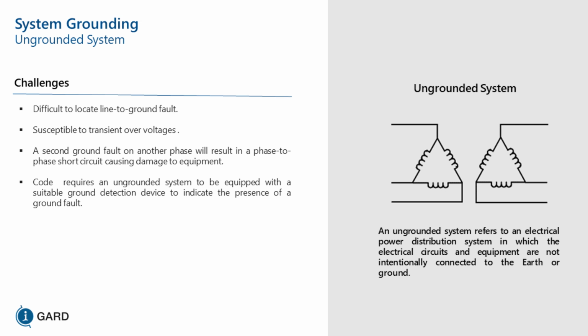So we're susceptible to transient overvoltages in an ungrounded system because, think of it as charging the capacitors of your system. You have an arcing fault, you're constantly charging and discharging the capacitors, and depending on the time of that fault, you could be arcing at the positive cycle of the AC wave or the negative cycle of the AC wave. So you're constantly changing the voltage on those capacitors, and you can have 6 to 8 times normal system voltage with respect to ground. If a second fault occurs, then you have a phase to ground to phase fault, and something will trip.